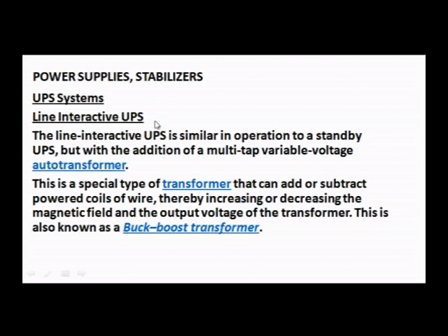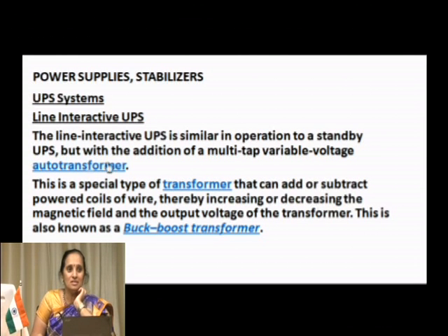Line interactive UPS is similar in operation to the standby UPS, but with the addition of a multi-tap variable voltage auto transformer. I can add or subtract the powered coils of wire, thereby increasing or decreasing the output voltage, as the magnetic field increases or decreases accordingly. So this can also be called a buck boost transformer - buck meaning reducing, boost meaning increasing.